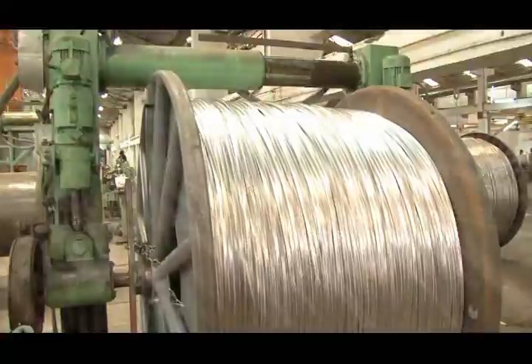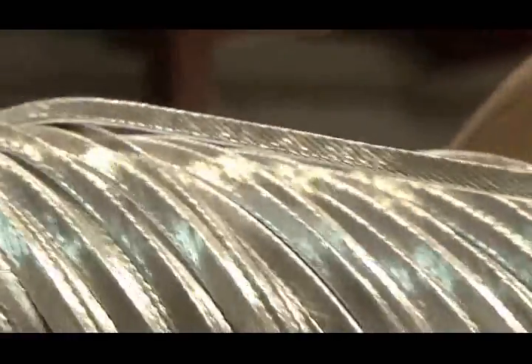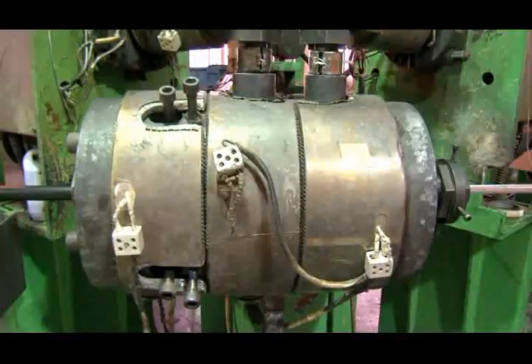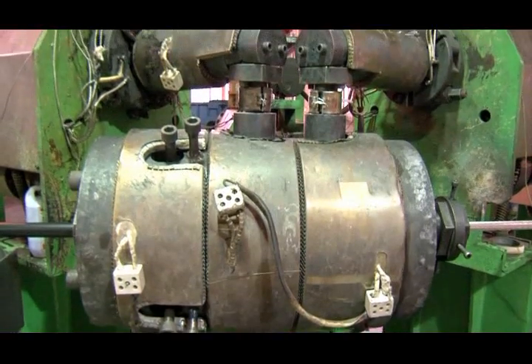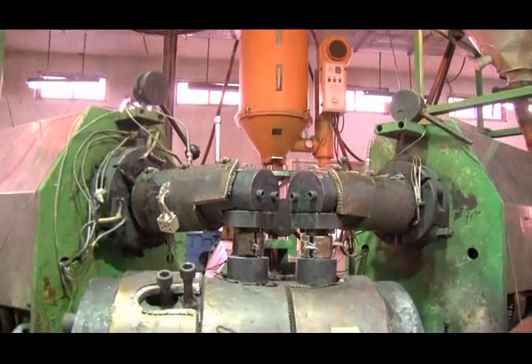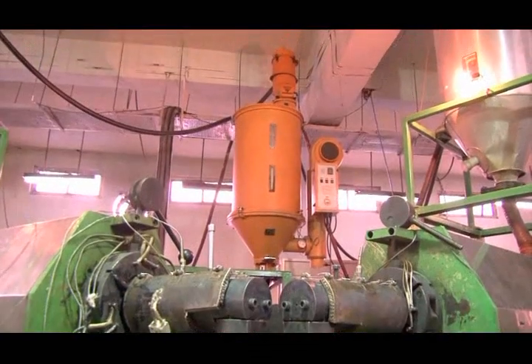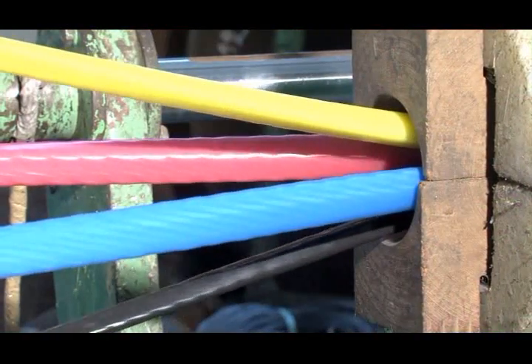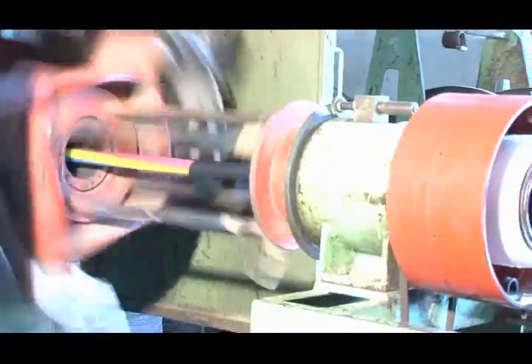The conductors are made from EC-grade stranded aluminum wires. Both insulation and insulation shielding are accomplished in a single operation using a special process. In case of multi-core cables, cores are stranded together and provided with a common covering of plastic tape wrapping.